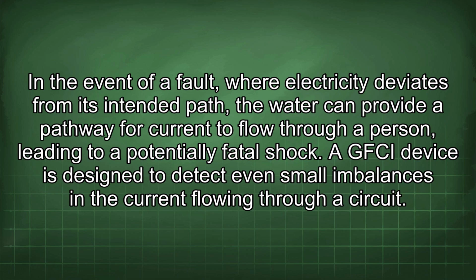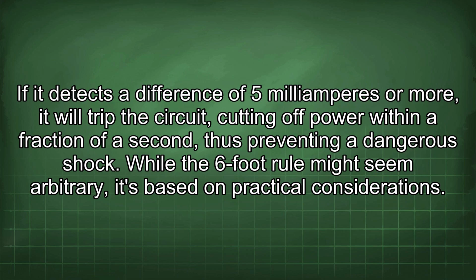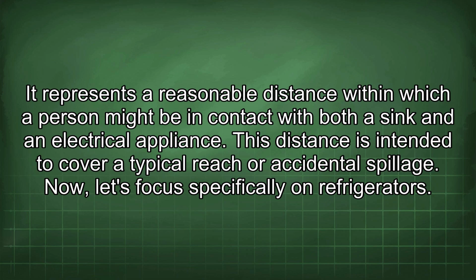A GFCI device is designed to detect even small imbalances in the current flowing through a circuit. If it detects a difference of 5 mA or more, it will trip the circuit, cutting off power within a fraction of a second, thus preventing a dangerous shock. While the 6-foot rule might seem arbitrary, it's based on practical considerations. It represents a reasonable distance within which a person might be in contact with both a sink and an electrical appliance. This distance is intended to cover a typical reach or accidental spillage.